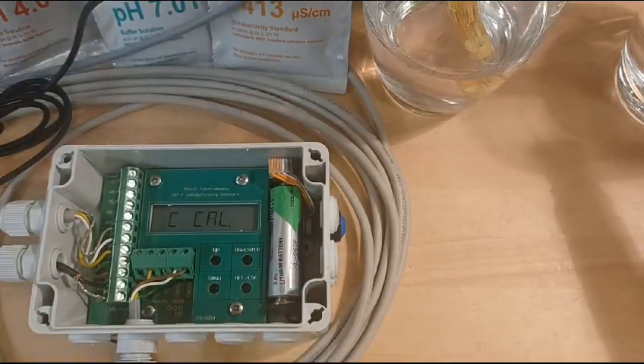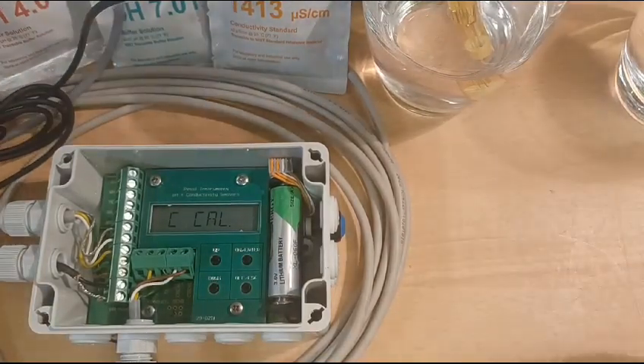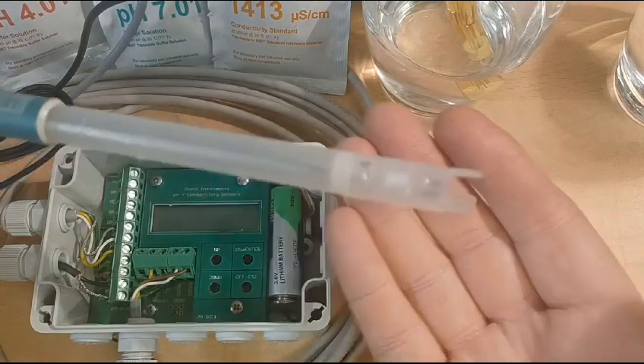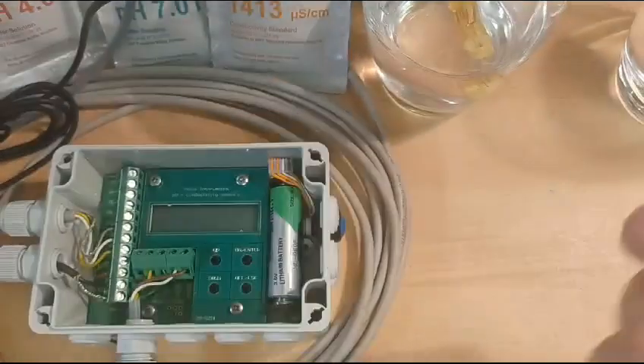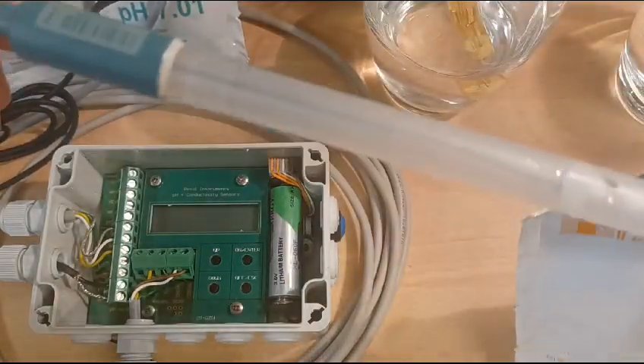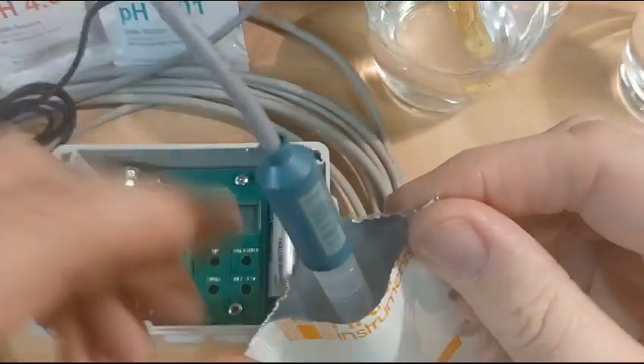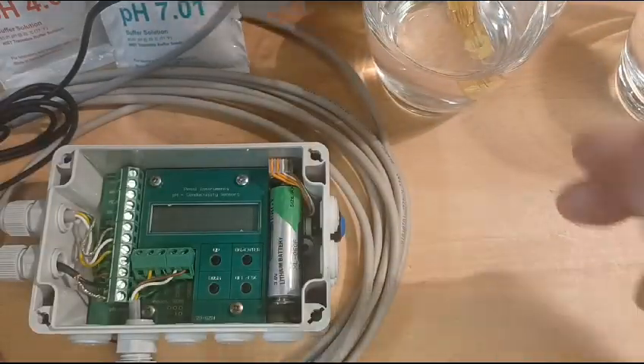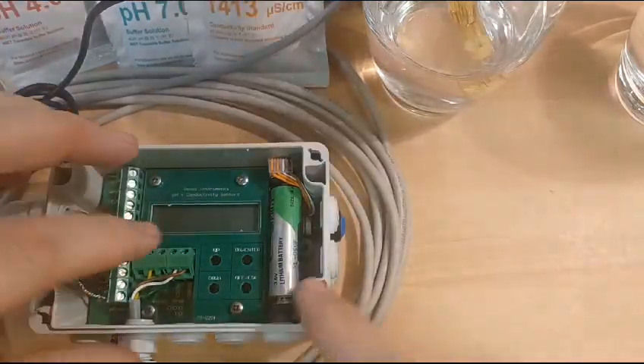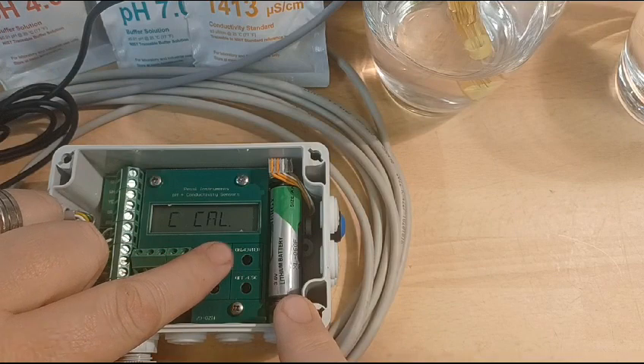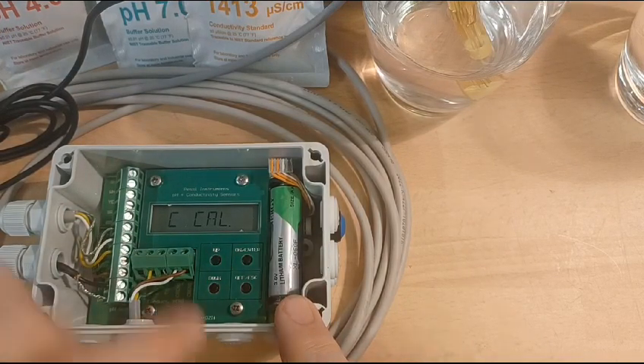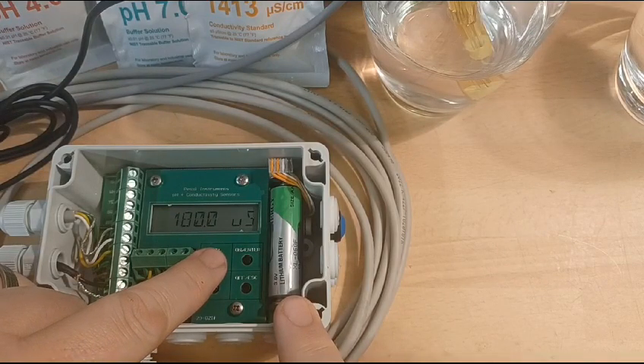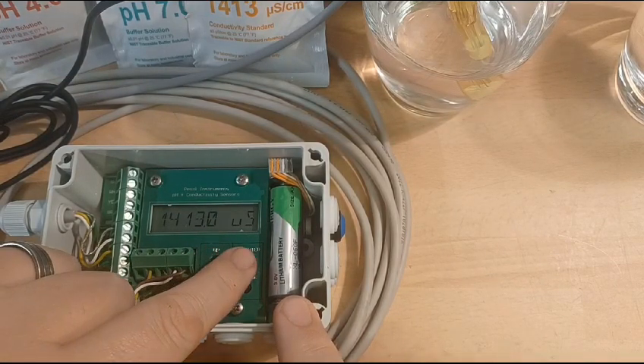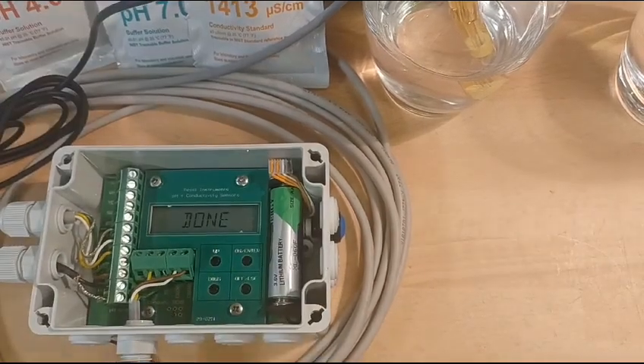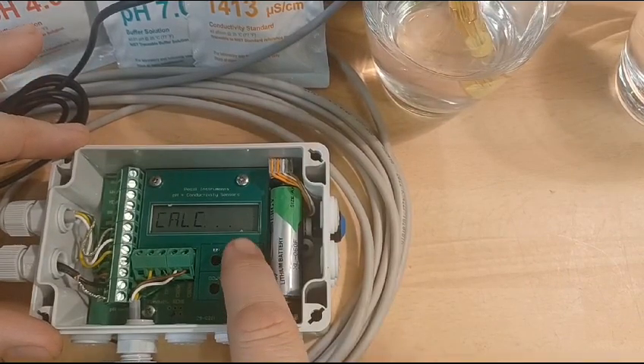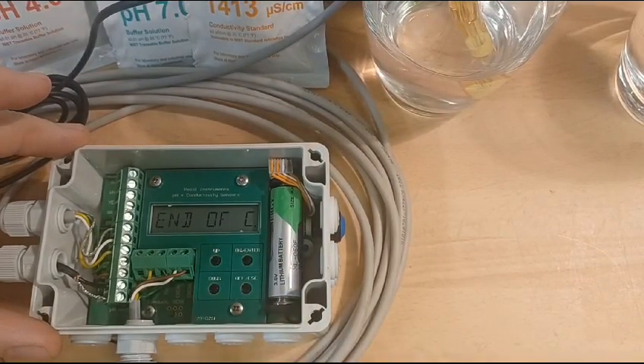Then the EC. This one, so it's not the glass one, has the two metal plates inside, and goes into the EC buffer solution, the 1413, just standing it off picture so it stands. Go to the menu and you want conductivity calibration, okay, and then just scroll up until you get 1413 and then okay. After a period of time, you'll then get the done message. Press OK, calculating OK, end of calculation.